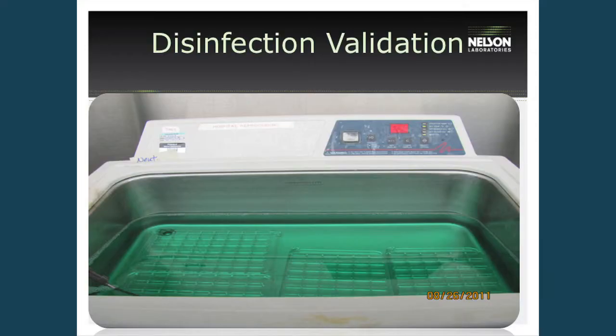All right, I'm going to quickly go through disinfection validations. Now these are different because for the disinfection validation, we're going to be utilizing a clean device. So the device has already gone through the whole cleaning process, and now we're testing to see if the liquid chemical disinfectant can properly disinfect the device.